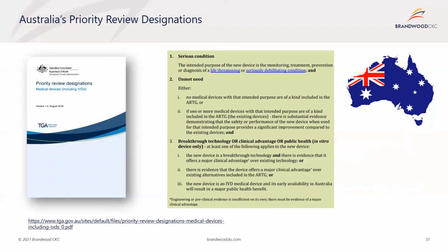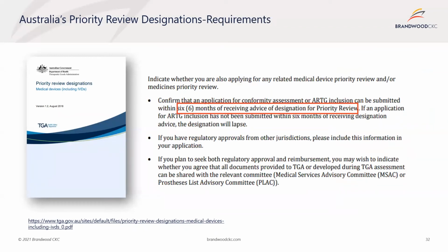However, it really should be used very differently from the FDA's approval process. Here's why. For a priority review designation, there is an expectation that the full application will be submitted 6 months after receiving the designation. That really means companies need to make this application when they're ready to submit the full documentation. It can't be longer than 6 months. There is a way to renew the priority review designation, but it's not advisable. I did want to mention there's a fee for this priority review application of about 9,000 Australian dollars as of 2018. The designation decisions, unlike the US, will be published on the TGA website after you have been notified.